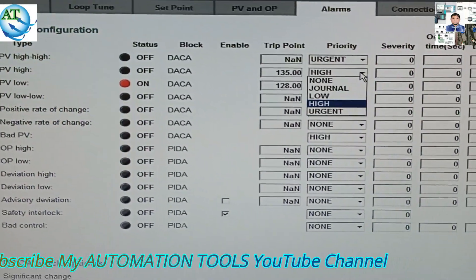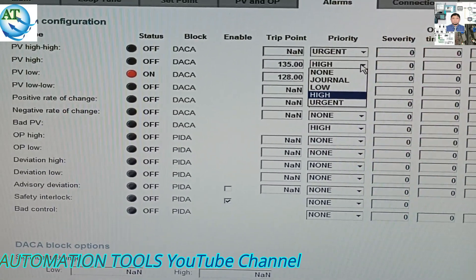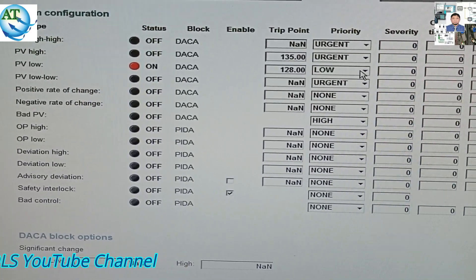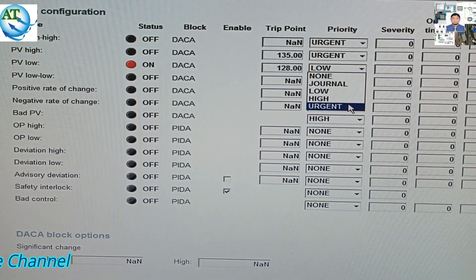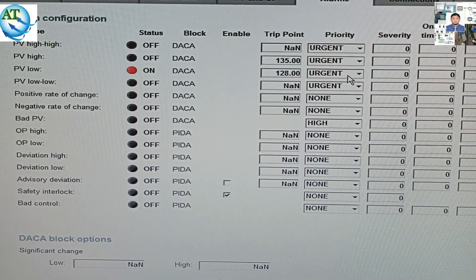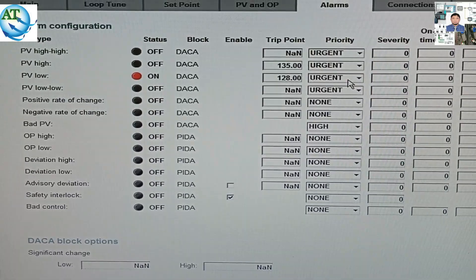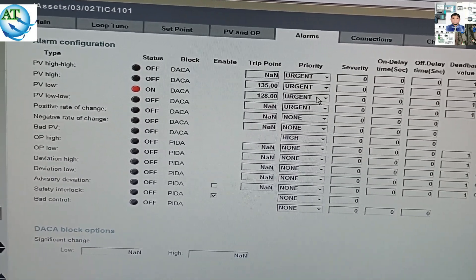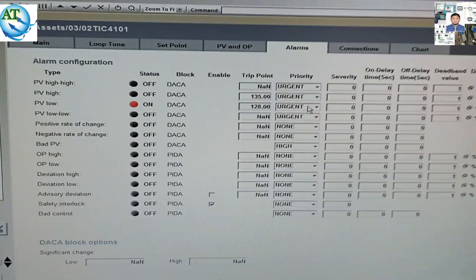You see it is showing the PV high alarm priority is high, so I will change it to urgent. After entering manager mode, the option is available. I am changing both: PV low to urgent and PV high to urgent. PV high alarm priority was high and is now urgent. PV low priority was low and I have now changed it to urgent priority. Our alarm priority change is now completed.